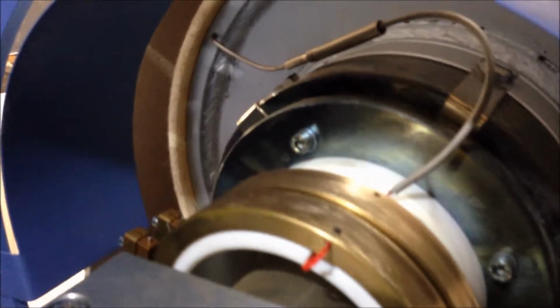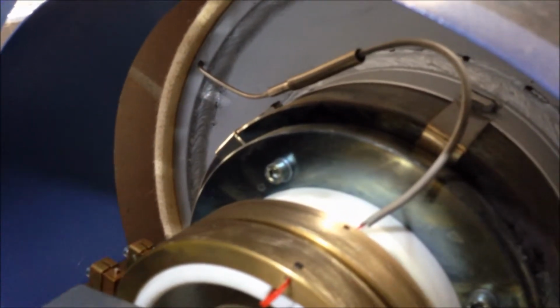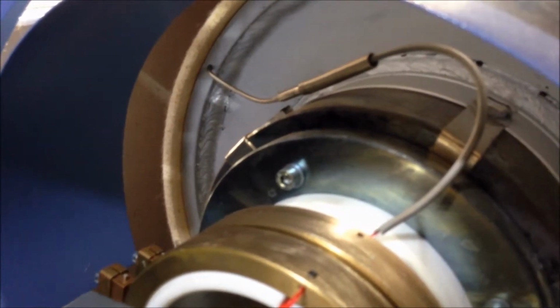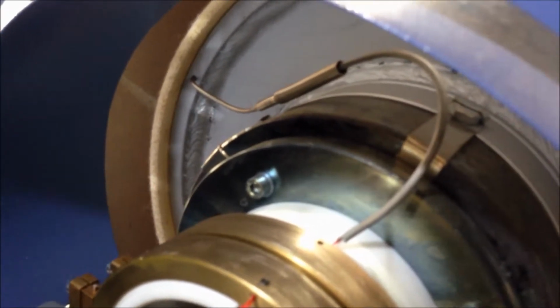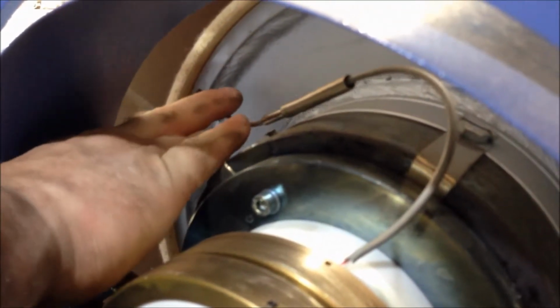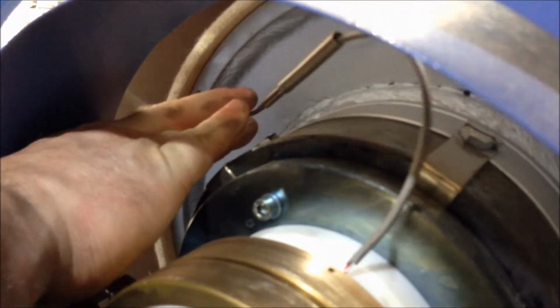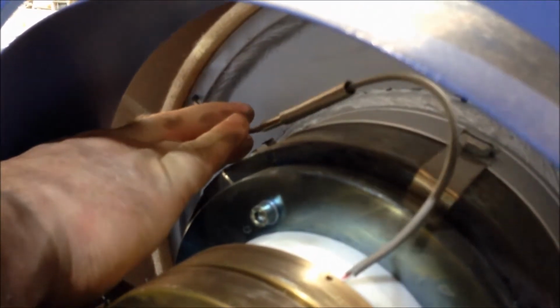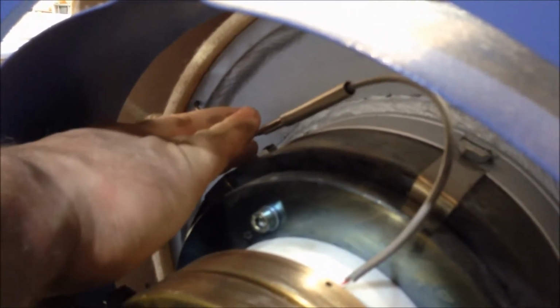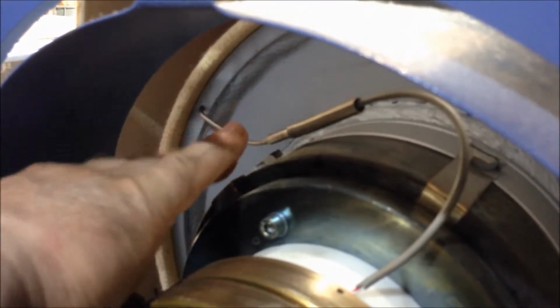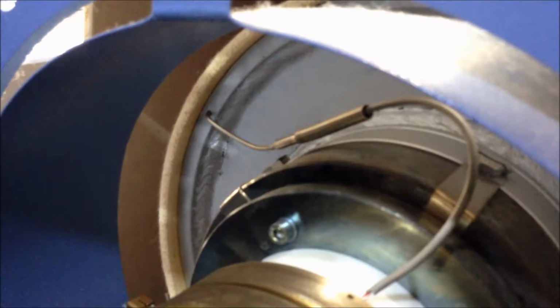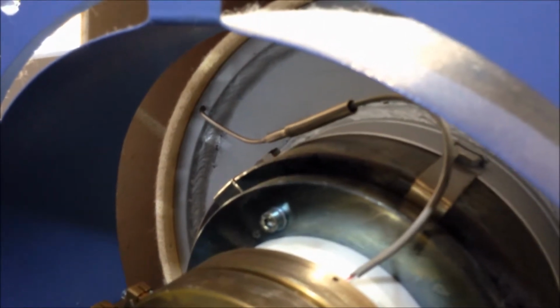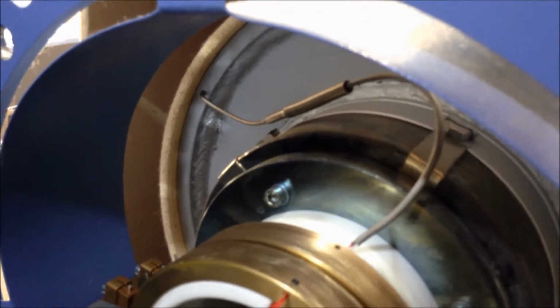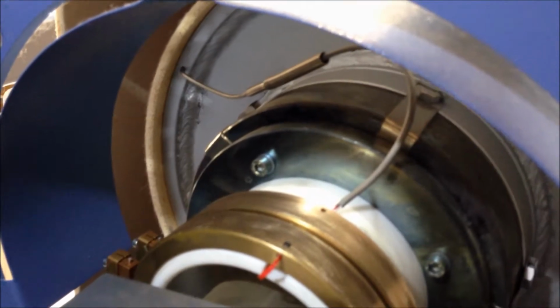What about the thermocouple itself? Isn't that it over there in the shell of the drum? Yes, there's your thermocouple right here in the drum. It's in there snugly. It doesn't have to be tight. You don't want it so tight that it doesn't move, but you don't want it loose where it's flopping. You want it to where it'll sit still. If it's not movable, then it's too tight. You've probably crushed your thermocouple. I wouldn't mess with it until you need a new one.